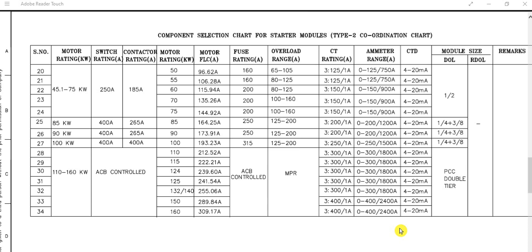So we are continuing the type 2 coordination chart for the starter module for DOL and RDOL starter. In the previous video we have seen the smaller size contactor operated starter modules, here contactor operated as well as breaker operated. Here you can see this is for 110 kilowatt to 160 kilowatt. These are ACB controlled, that means air circuit breaker.